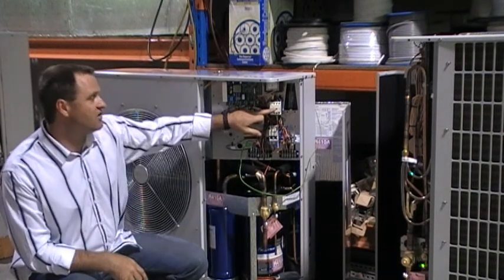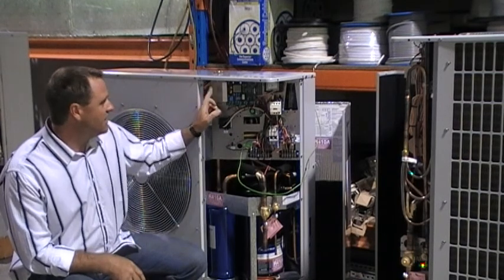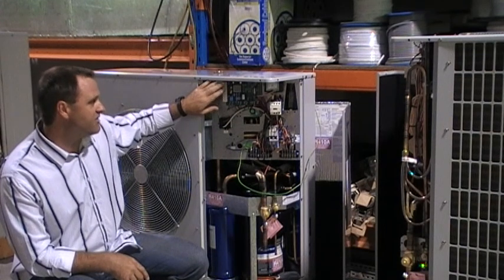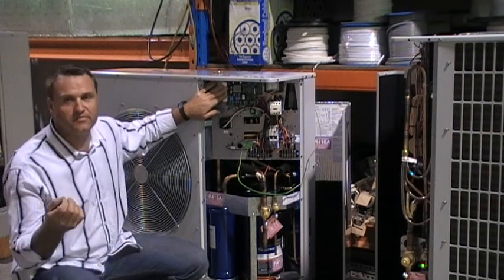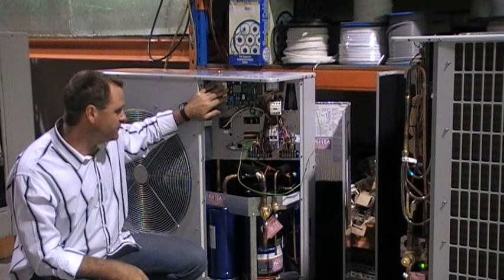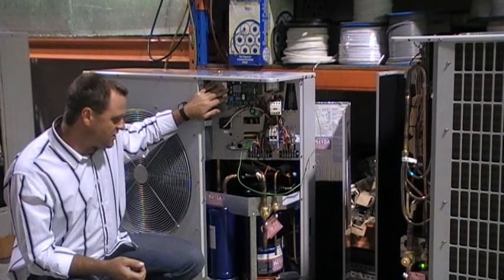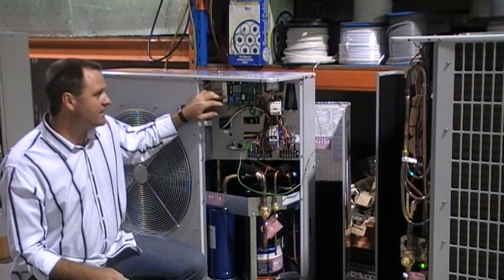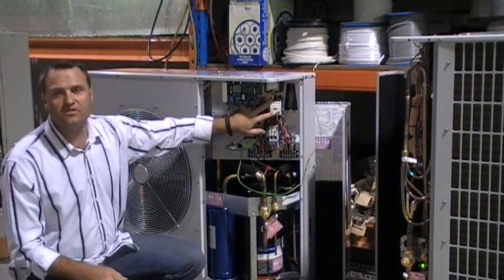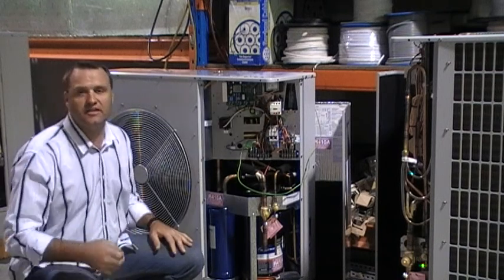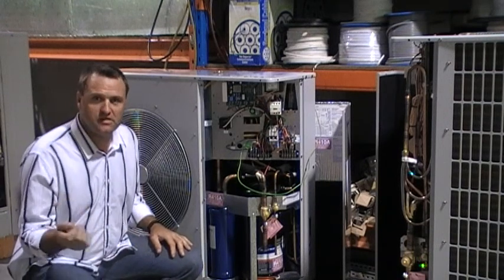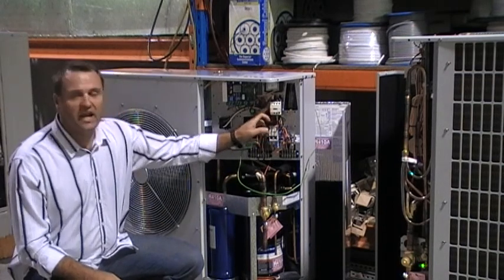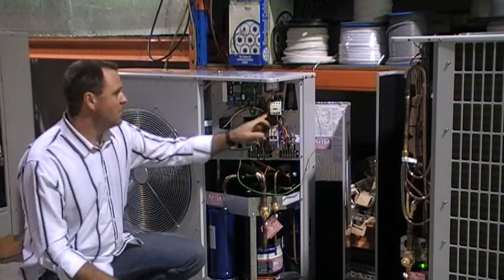It does this via a contactor, and nowadays most of the units have a PC board that talks to the electronic controller inside. The advantages of a standard cycling unit are, for one, they use simple switching, which is a contactor. Now I can buy a contactor from any one of the local suppliers off the shelf. It doesn't have to be from this manufacturer, any contactor off the shelf will do.